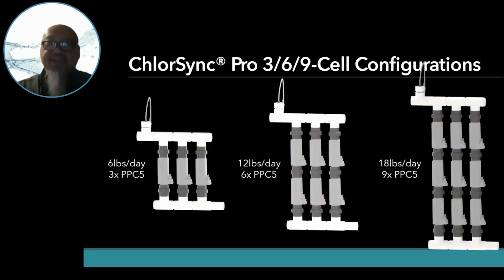On the manifold configuration, you can see we've got a 3, 6, or 9 cell configuration. There's a single tri-sensor, as you can see on the top right, and a header that goes into the 3 banks of cells. If you only need 2 cells, there'd be a dummy cell in that third position. If you only needed 5 cells, you'd have 5 actual cells and another dummy cell, or for 4 cells, 2 dummy cells. This gives us the capability of expanding.